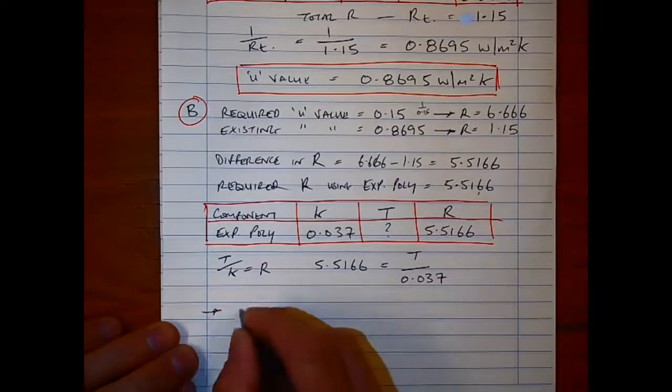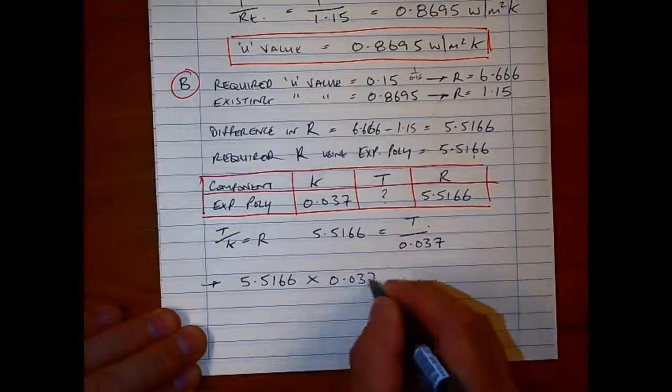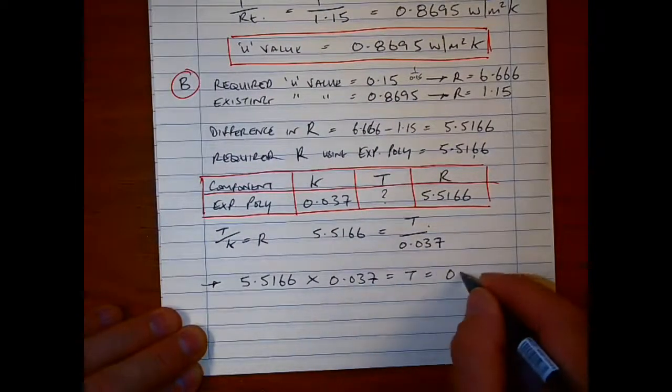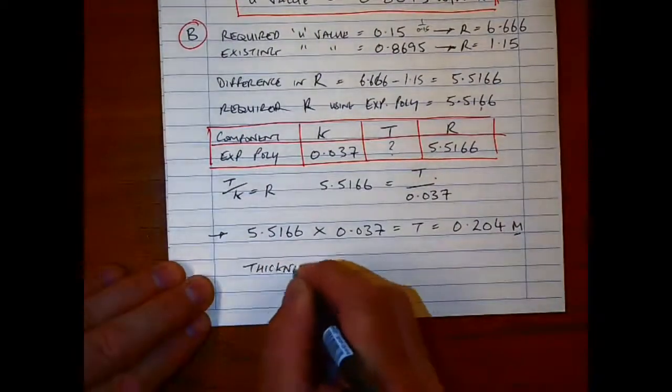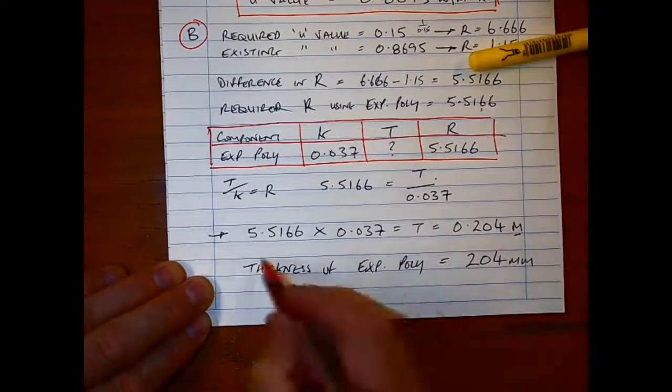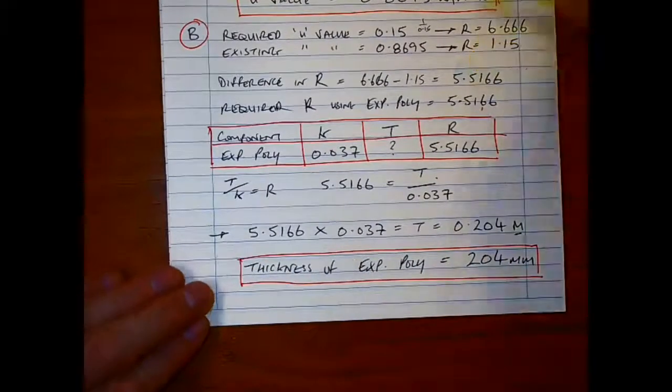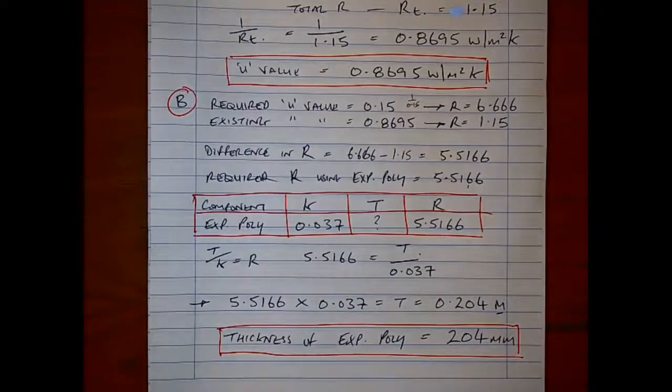We just don't know the thickness, so we go back to the formula with the thickness and the conductivity. You can see I'm writing it out here. All I do is divide one side—I take it over to the other side—so I have to multiply it. I multiply the resistance by the conductivity, which will give me my thickness. It's in meters, so I change it to millimeters. So it's 204 millimeters, as simple as that.